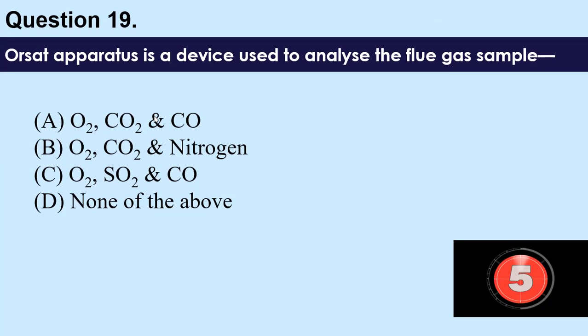Question number 19: The Orsat apparatus is a device used to analyze the flue gas sample for — A) O2, CO2, and carbon monoxide, B) O2, CO2, and nitrogen, C) O2, SO2, and carbon monoxide, D) none of the above. The answer is A — oxygen, carbon dioxide, and carbon monoxide. The absorbents used are potassium hydroxide (caustic KOH) for CO2, pyrogallic acid for O2, and cuprous chloride for carbon monoxide.